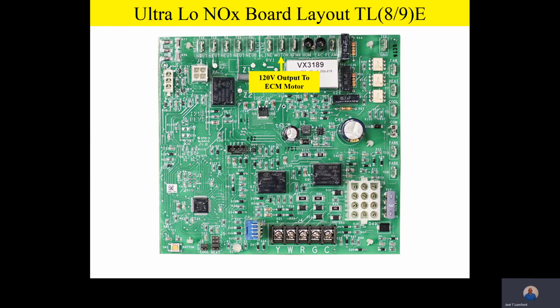And by the way, that ECM means electronically commutated motor. That's just a fancy name for a high efficiency motor. Now, it should be noted, all ECM motors have power to them all the time. So anytime the furnace is powered up, you've got power to that ECM motor. Now watch this, the motor's just sitting there waiting for 24 volt commands to tell it what to do.